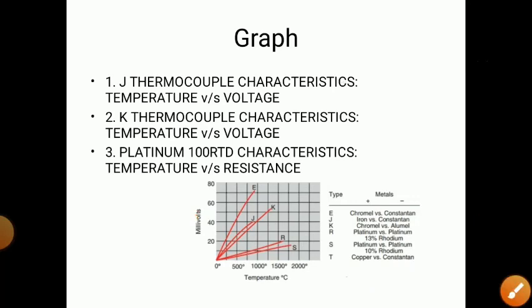The graph is plotted with temperature in degrees Celsius on the x-axis and millivolts on the y-axis. Both J type and K type thermocouple characteristics are almost linear. K type is very linear while J type is slightly non-linear.